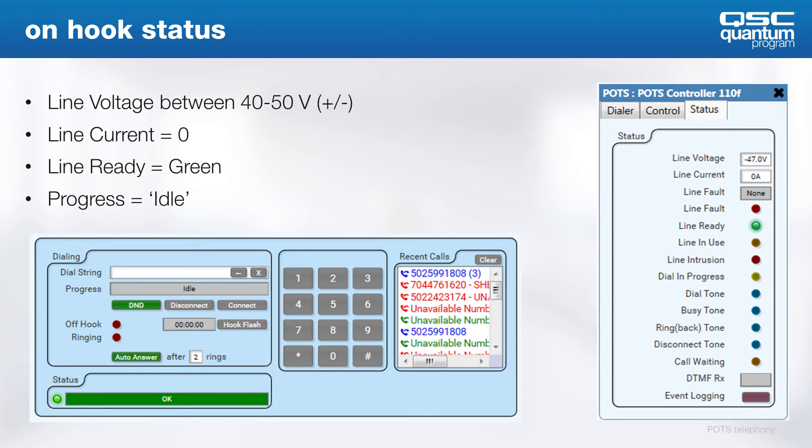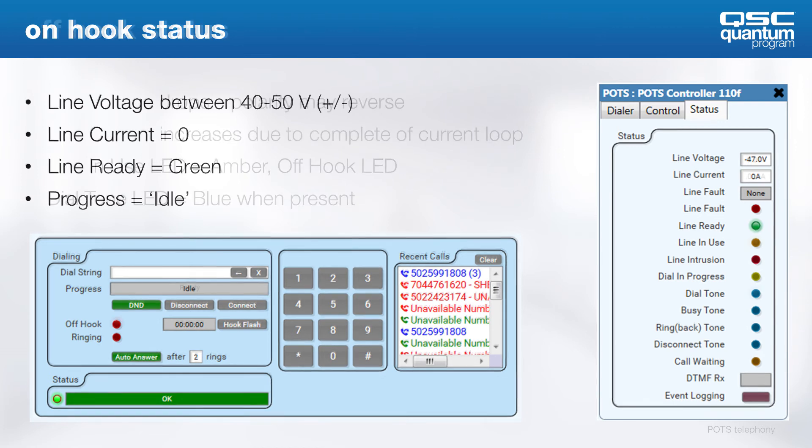When you have it on hook with a good line, you'll see that the line voltage is between 40 and 50 volts, keeping in mind that polarity doesn't matter, and the line current should always be 0 amps. You see a lit line ready LED, and the call progress on the dialer should read idle at this state.